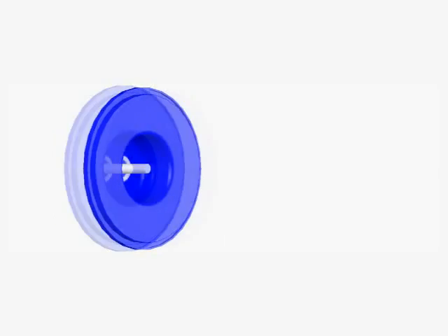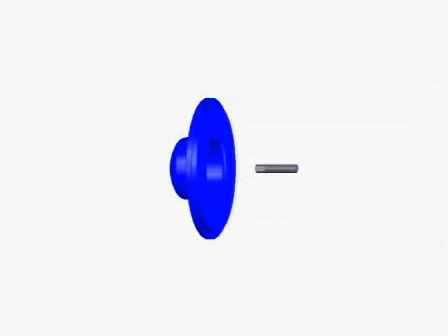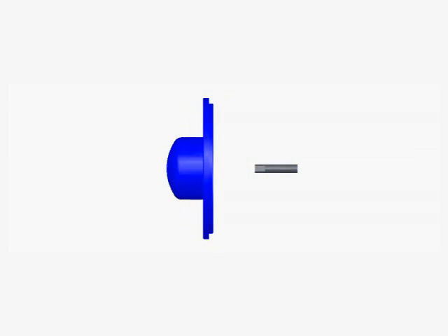For aggressive fluids or abrasives, Teflon, alumina ceramic, and silicon carbide bushing packages are available. A simply supported replaceable impeller shaft is offered in alumina ceramic, silicon carbide, and Hastelloy. The elliptical shaped barrier distributes stress equally over its surface, resulting in the capability to withstand extreme working pressures.